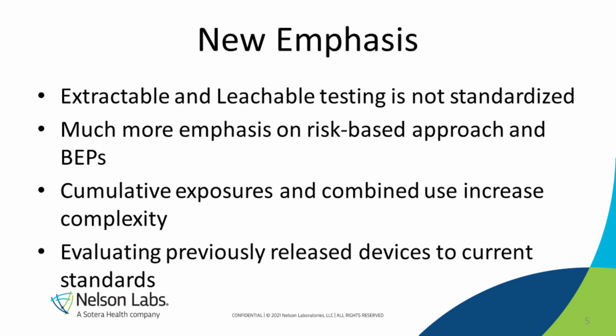So for lots of high-risk devices, maybe material information does not give you enough information to be able to do an evaluation. Then you add to that by doing extractables and leachables testing, which is just looking at the chemicals that come off your devices and understanding the toxicological risk from that. Now, the hard part is that extractables and leachables testing is not standardized. We're getting better. There's a new 10993-18 that's just recently come out that really helps standardize more of this chemistry testing. But labs do it a little bit differently. Some labs that do it differently are still very good, but there are some labs out there that honestly haven't quite met the requirements of the new standards. So that's part of the problem.